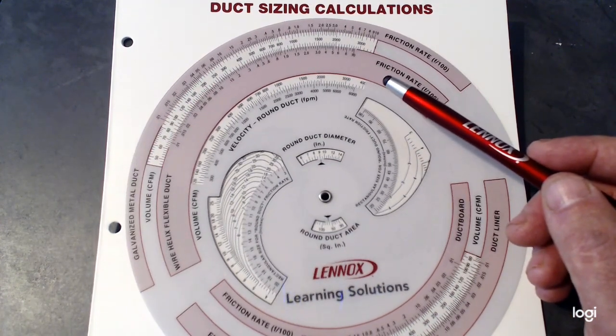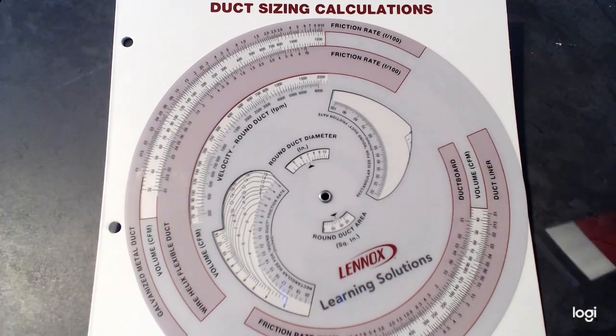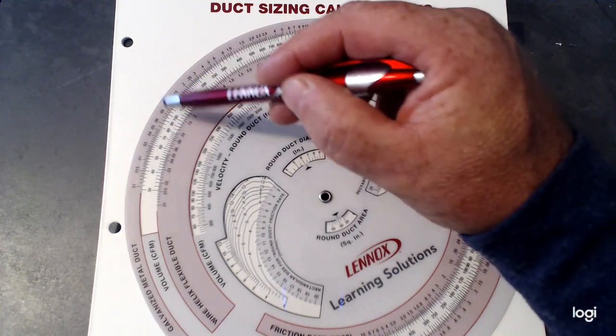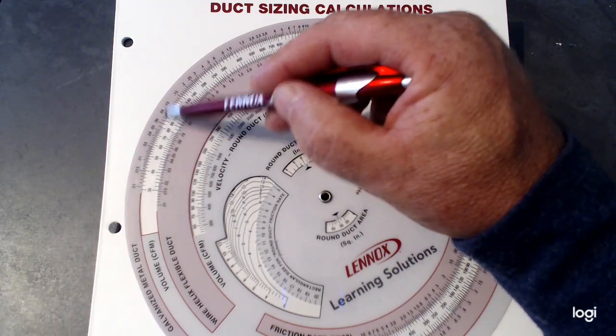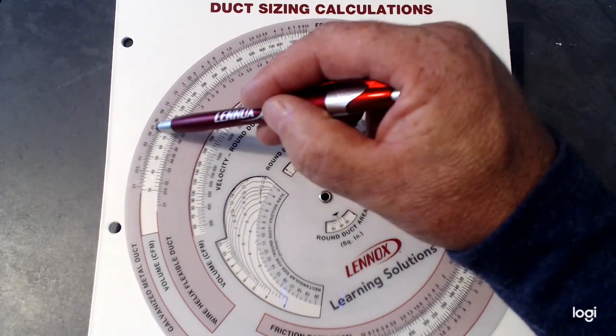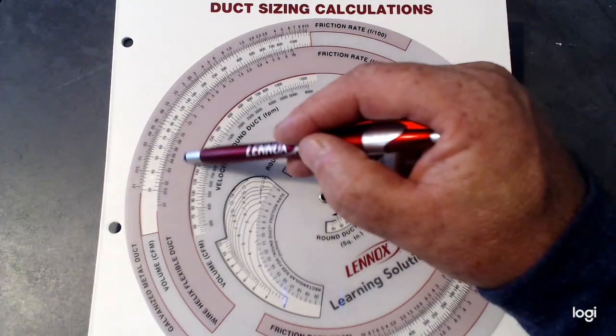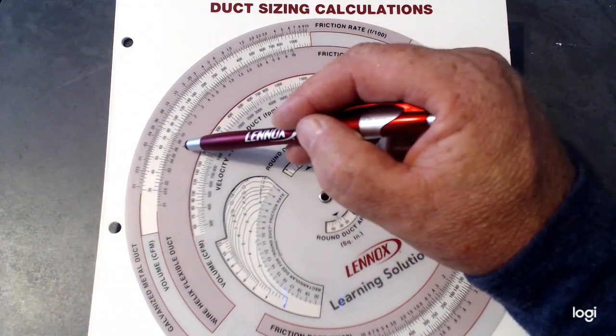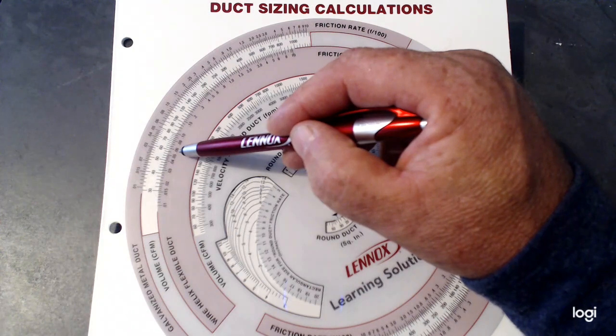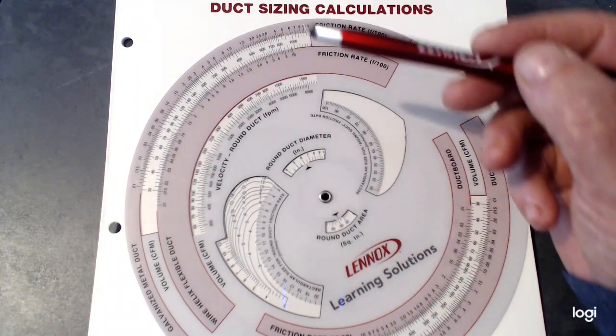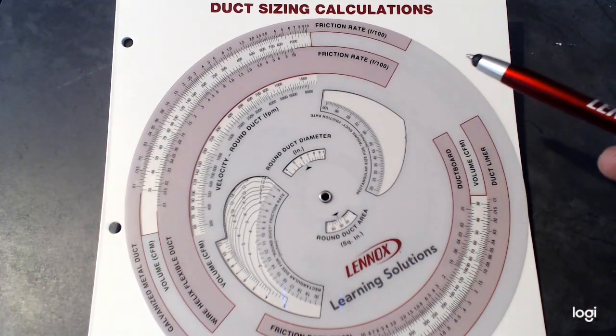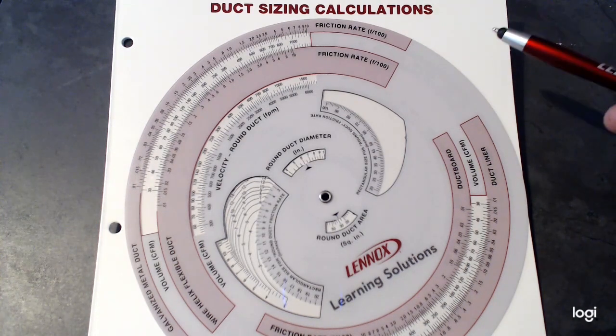First, we're going to start with the 6-inch duct. If we move the duct diameter calculator to 6 and use the 0.06 number we obtained earlier, we'll see on the metal side that it's somewhere around 85 CFM. Note that at 0.08, it's somewhere around 100 CFM — and 100 CFM for metal is the number most of us are used to. If we were to use 0.08 for flex, we see that's 70 CFM, and at our 0.06, it's 60 CFM. As a service or field technician, using somewhere between 0.06 and 0.08 will get us close. Remember, the calculation we did earlier is for one specific duct job, and every single house is different.